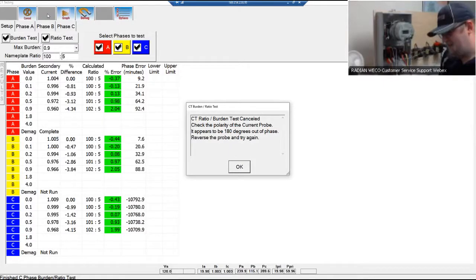So if you were able to hear that, the RW beeps irregularly, saying that there was an issue. The issue it just said was the polarity of your current probe might be a bit off. You might need to not do what I did and swap it the right direction. With that, it'll tell you if it thinks the probe's off, and it does that by measuring phase error in minutes. Minutes being 60 minutes for every 1 degree. So it's reading negative 10,000 minutes with this, thinking that I've got my probe on backwards. So it warns me saying, hey, you might want to retry that test.